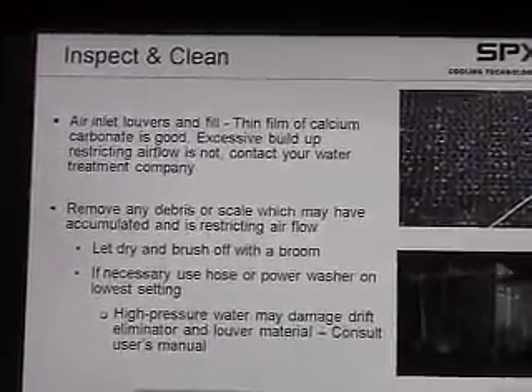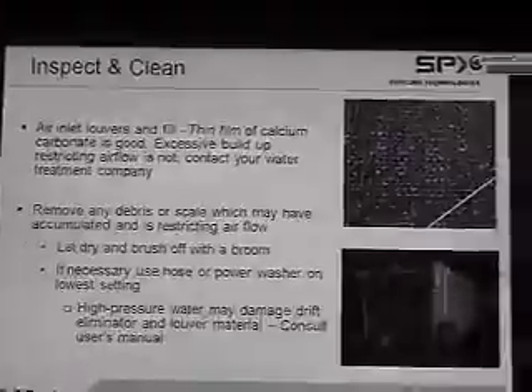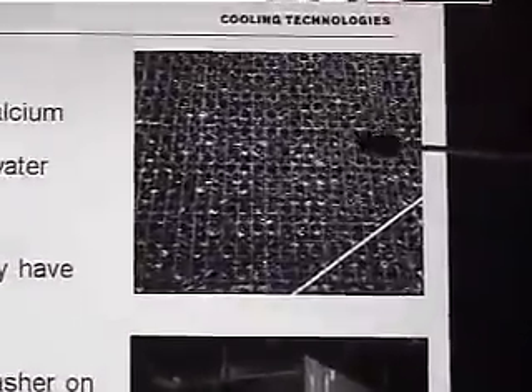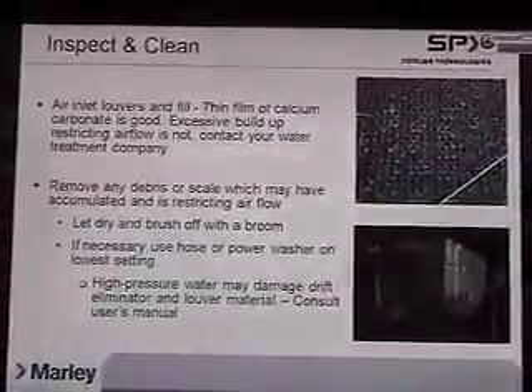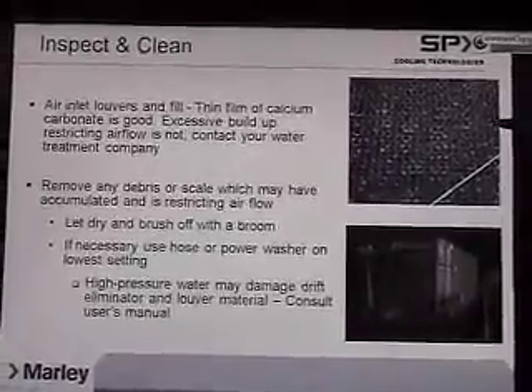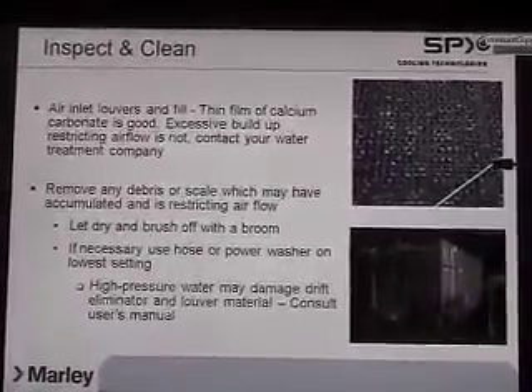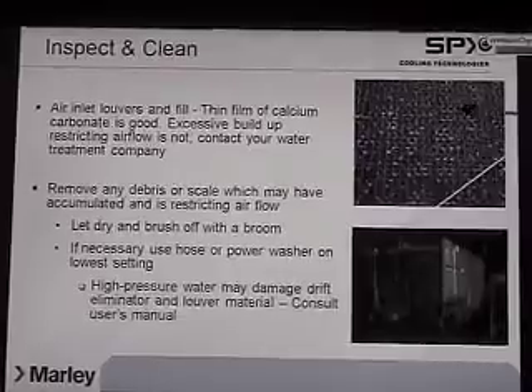This is a picture of some clogged fill. Again, that's scale, and proper water treatment would help prevent that. Sometimes people want to clean their fill or their drift eliminators, and they want to use a high pressure sprayer. That just damages the fill. This is just PVC plastic, and it just makes it all ratty. It can tear up into little pieces. It can get in your condenser water and get in your equipment.